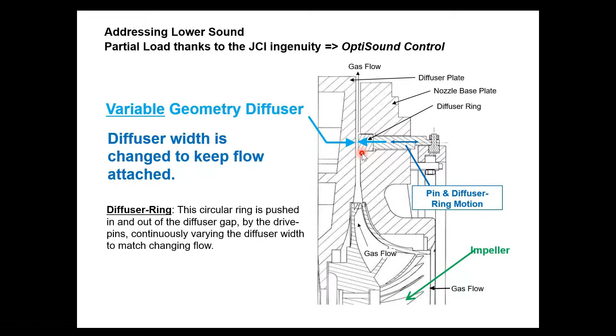This is just being adapted, or this is just kept as an option in centrifugal chiller, so that at low load condition it doesn't surge, and in case of high lift requirement, it is able to generate that high lift, because it will prevent the centrifugal chiller from getting stalled. So with this centrifugal chiller, surge line actually shifts up.